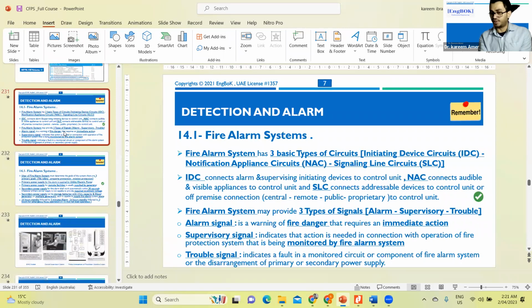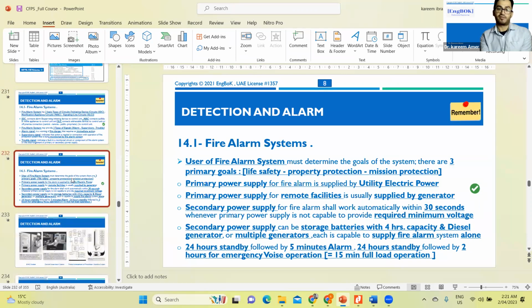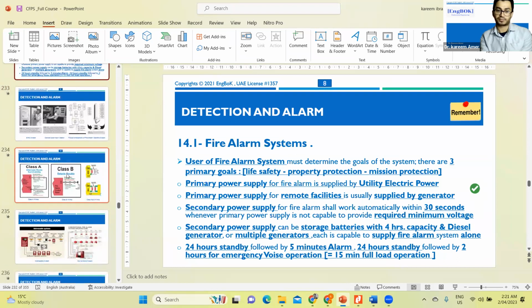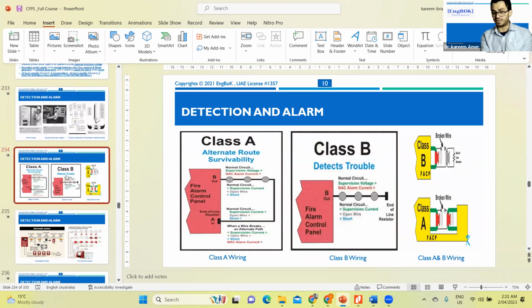We cover the types of circuits required and signaling in the fire alarm system: what is the supervisory signal, the trouble signal, the alarm signal, the supervising station, the type of power supply - secondary and primary - and how you calculate battery size. What is class A, class B wiring inside the fire alarm or detection system?